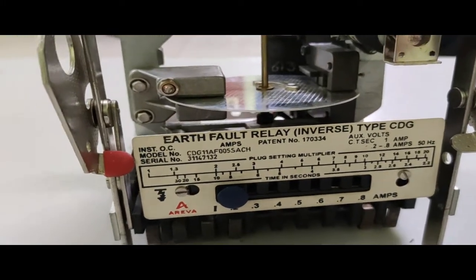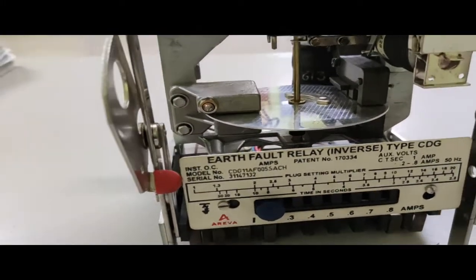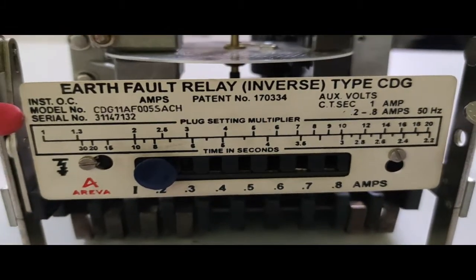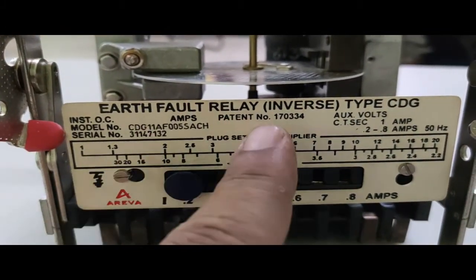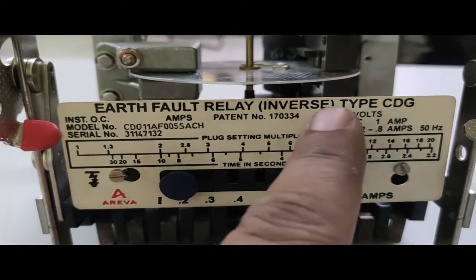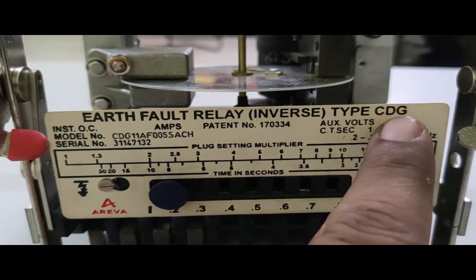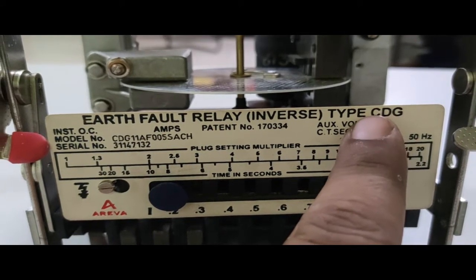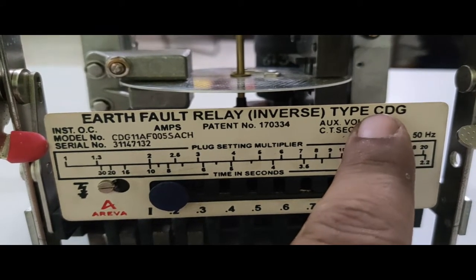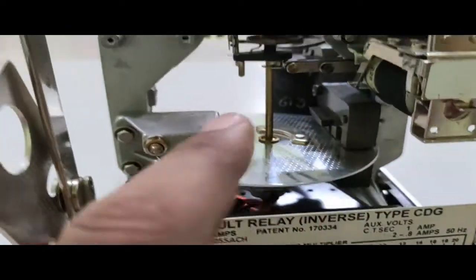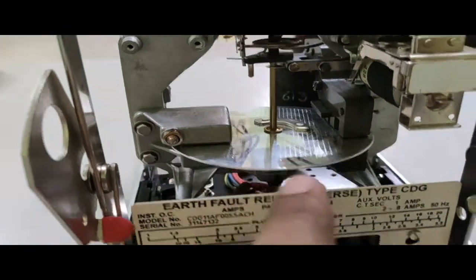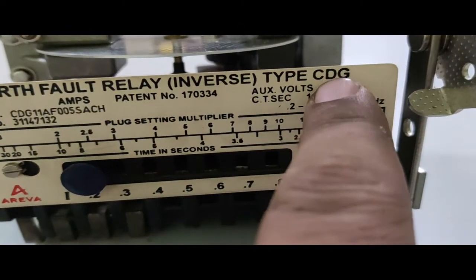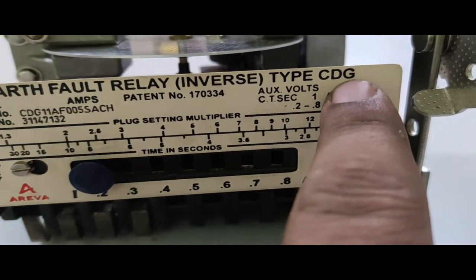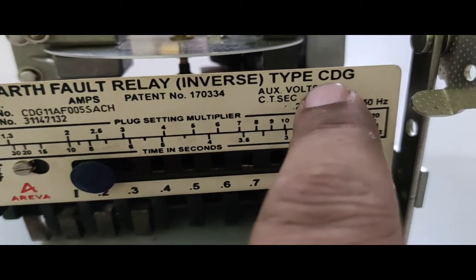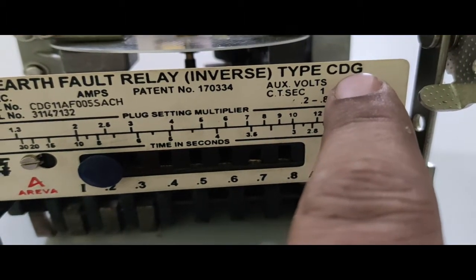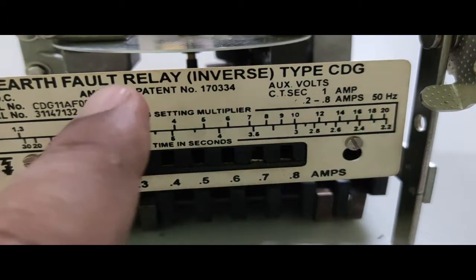Hello everybody, let's see the operation of the electromechanical induction type relay. This is the nameplate of the relay. Here it is written that this is the earth fault relay and it's an inverse type, and the type of the relay is CDG. Now what is the meaning of CDG? C means it's a current operated relay, D means it's a disc type relay, because you see some aluminum discs are there, and G means the relay characteristics follow the IDMT curve. Later on I will explain the IDMT characteristics of the relay and also the inverse type relay.